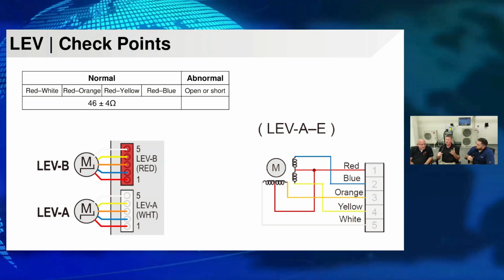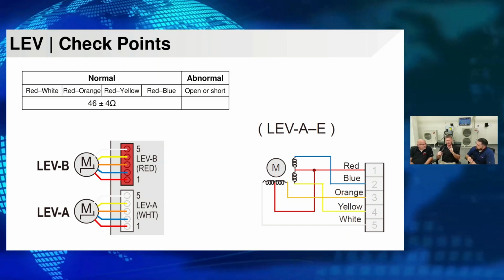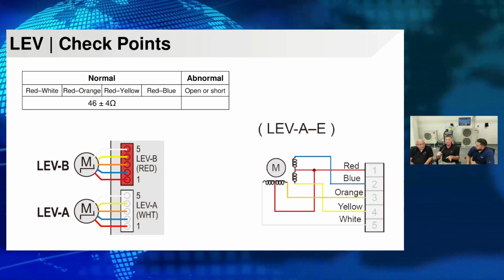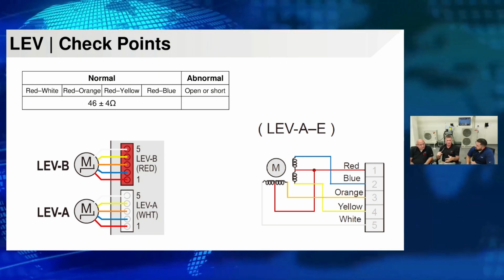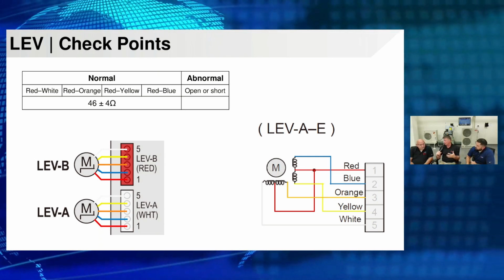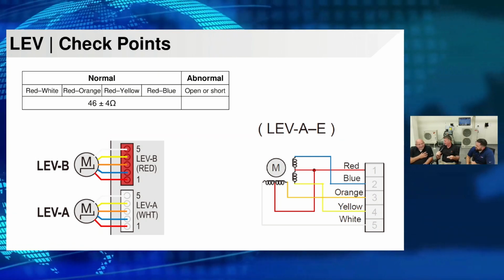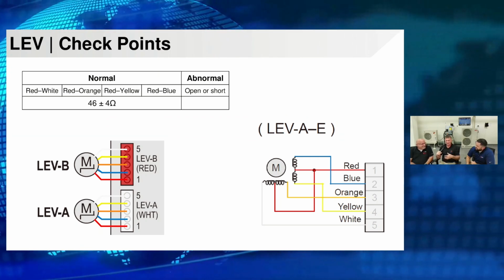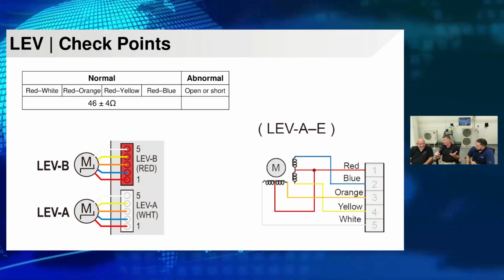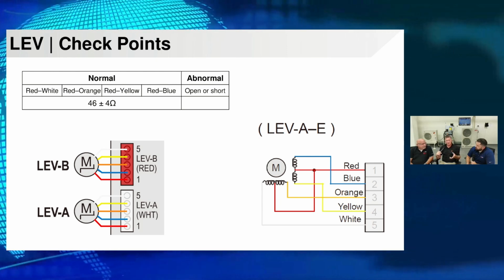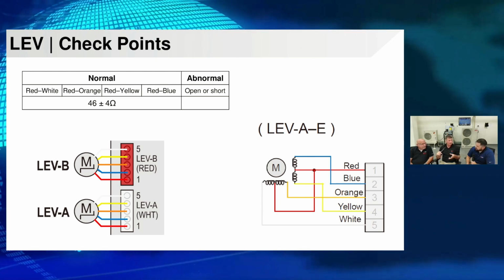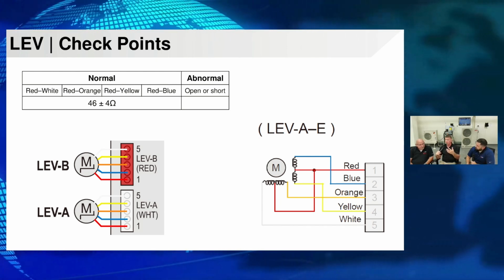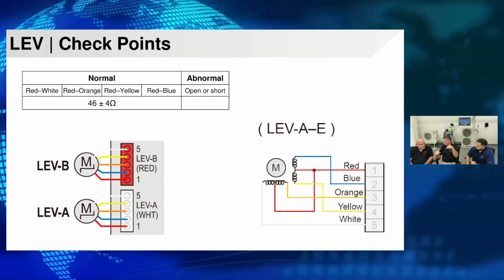I've actually encountered, I've only found one in my life. I had a system that would not modulate to 100% capacity. It wasn't yours, by the way. It wouldn't modulate to 100% capacity. It would only operate up to approximately 80% capacity. And what we found is that one of the windings was actually bad. So it would operate, but it couldn't open all of the way.